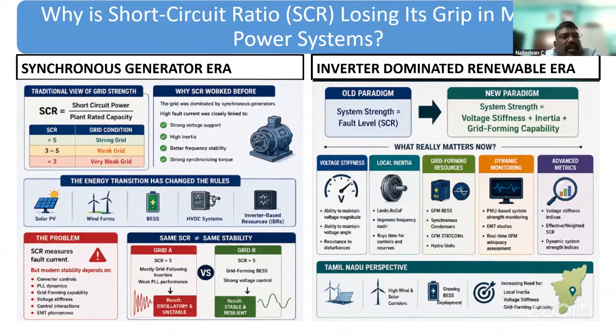The short circuit ratio is equal to short circuit power divided by plant rated capacity. If the grid has a short circuit ratio greater than 5, it is normally termed a strong grid. When the ratio is on average 3 to 5, the grid is weak. If it is much less than 3, it is marked as a very weak grid.